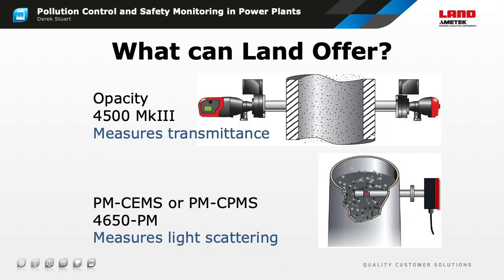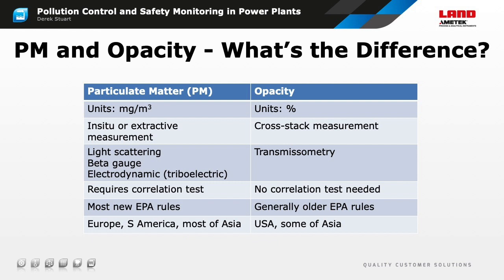AMETEK Land offers 2 different sensing technologies for measuring particles in flue gases. The 4500 Mark III is a traditional opacity monitor measuring the amount of light transmitted across the stack. It can be used in most power generation applications in North America, especially those where the emission limits are set in percentage opacity. The 4650 PM probe uses laser light scattering to measure low-level dust concentrations in the cleanest processes. It can also be used in power generation applications subject to the US EPA's Mercury and Air Toxics, or MATS rule.